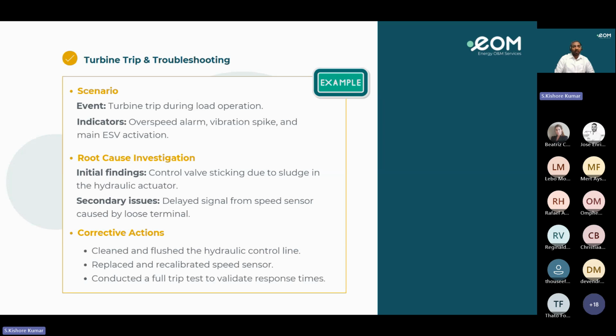And I already spoke about the vibration spikes. Sometimes the vibration sensor is not calibrated well. Sometimes there is a loose connection. Sometimes operators think, why do we have to check, the plant is running well. Over a period of time there is a loose contact. Some sensors may be damaged, or some sensor tips may be damaged. This will cause the vibration spikes.